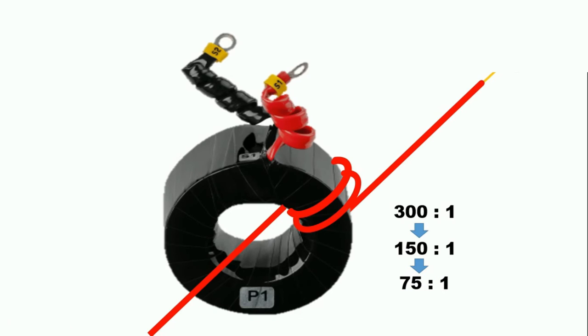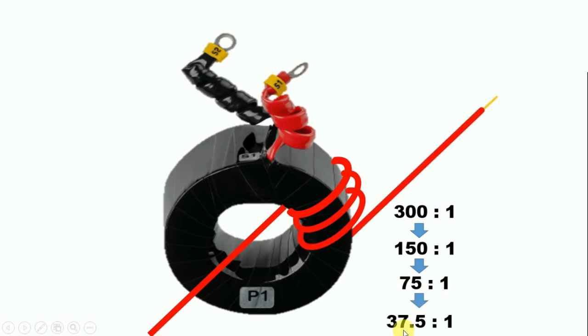Now suppose we have to reduce the ratio again. We add one more turn around the CT. The ratio will become half of 75 by 1, that is, 37.5 by 1. So in this way, we change the ratio of CT.